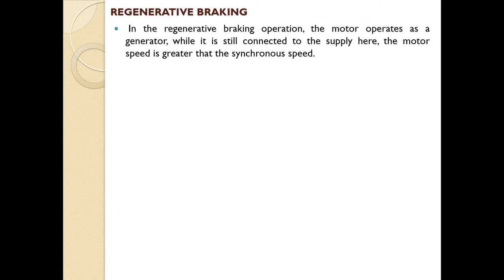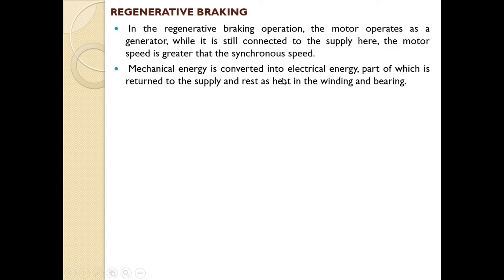In regenerative braking operation, the motor operates as a generator while it is still connected to the supply. Here, the motor speed is greater than the synchronous speed. If the motor is a DC motor, the speed of the motor will be greater than the no-load speed. Mechanical energy is converted into electrical energy, part of which is returned to the supply and the rest dissipated as heat in the winding or bearing.